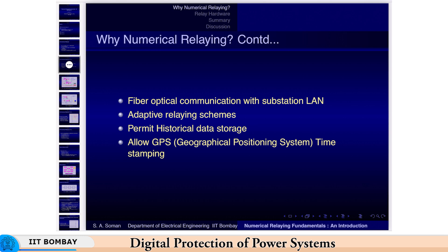One advantage in recent times is that the clock used for sampling can be the GPS timestamp, GPS time, so you can do simultaneous sampling all over the network. This came mainly with phasor measurement units, which we will discuss a little later. But now this is available for relays also, and you can use the timestamps - you can either have a direct GPS receiver, or the relay has a port known as the timing port, the IRIG-B port, where you can give a signal available at your substation from a GPS, and have a proper timestamp so you can compare data across locations.